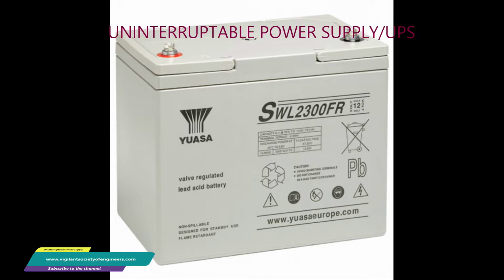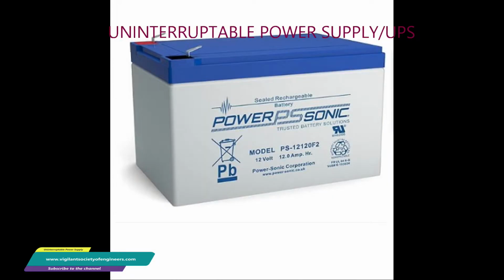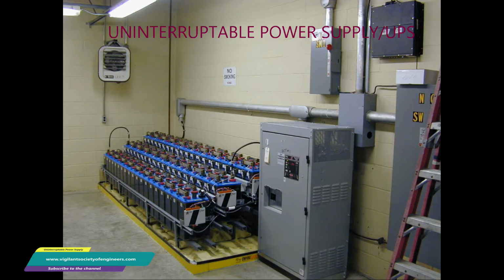Now, all batteries are kept charged by use of a rectifier or the charger. The battery storage capacity is a measure of the ampere hour, that's the number of amperes of current that the battery can supply for an hour. Autonomy is the length of time in minutes of the available electrical power stored ready for use. Simply explained, it is the length of time the VRLA batteries will support the UPS load.